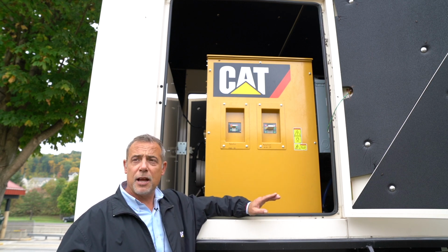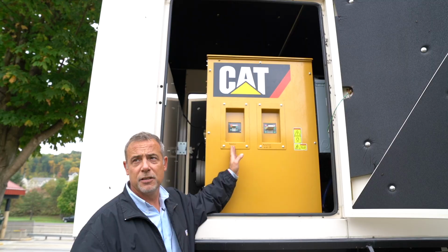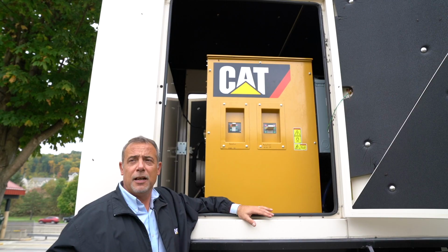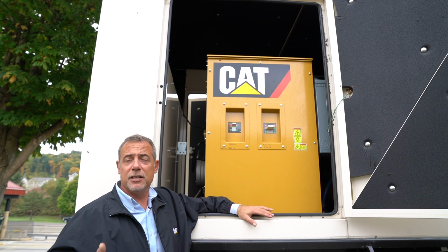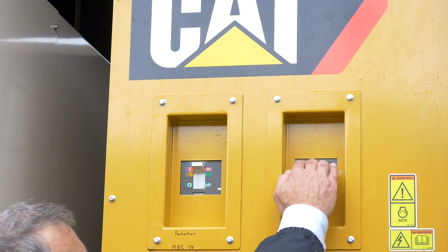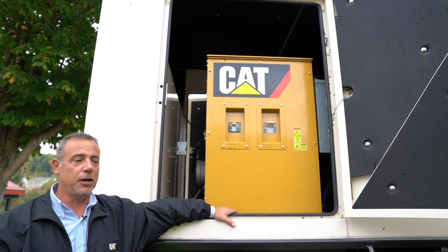When you have the emergency stop like we had earlier that we reset, the final stage was to reset the breakers. You're going to have to pull the breaker down and push it back up. And if the fault is not reset, it's not going to let you reset the breaker. That's the last thing you do after you reset a fault. Make sure the breakers are shut.